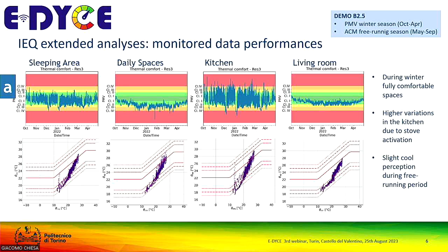And after that, we also see that in summer, in the free running, we have a fantastic control, we can say, in some way even slightly cold, even if outdoor conditions are very hot, because it's a massive building, and clearly the tenants have already done a correct management of the rooms. Now we see that it's more compact. We also see that this part is more south facing in respect to the others, and in fact may have some more peaks from the comfort point of view.